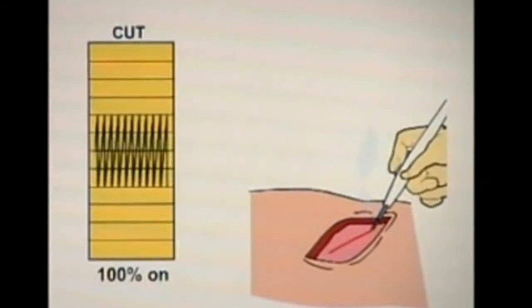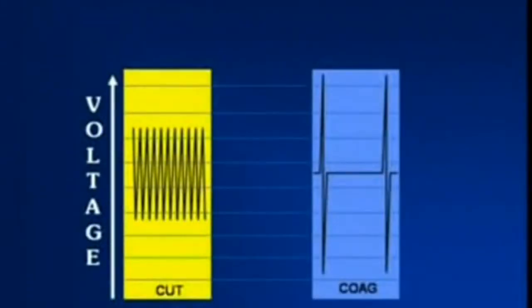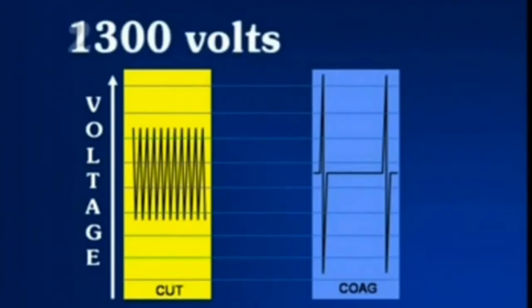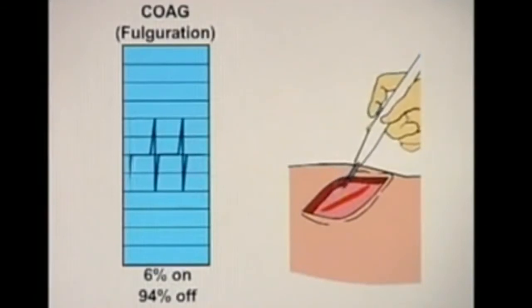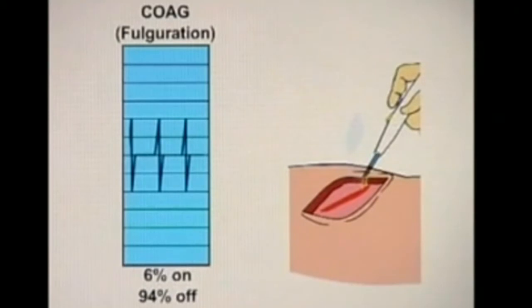There are two important differences between these: the time the current is actually supplied by the generator and the voltage. To achieve the precise, clean cut one gets in the pure cutting mode, the power is on 100% of the time, leading to rapid and extreme heating of the tissues, which vaporizes cells. Pure cutting current is used, for example, to open the skin. The voltage used in cut is substantially lower than in coagulation mode, with peak voltages ranging from approximately 1300 to 2300 volts. To give the hemostasis associated with coagulation, the power is delivered in pulses and is actually on for only about 6% of the time. This results in much less heat generation, so instead of being vaporized, the tissue is heated more slowly and chars.